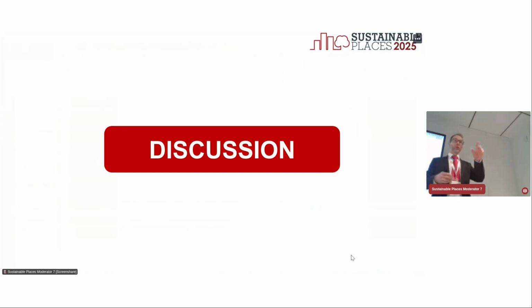Back to this, we have two solutions. We also have very modern buildings, but the renovation rate in Europe is low, so retrofit is absolutely necessary - we can't make everything new with 25 degree heating. We also have the Swiss pilot with three temperature levels: 18, 25, and 60 degrees. There's another solution where parallel systems reject heat from the rack, allowing us to serve three independent systems of the building at three temperature levels.